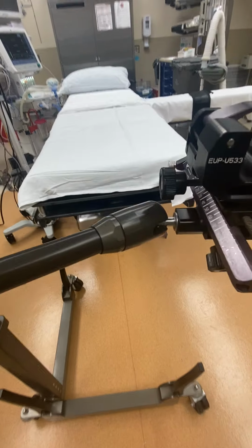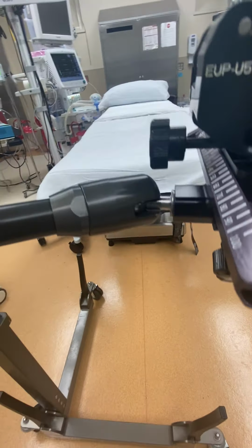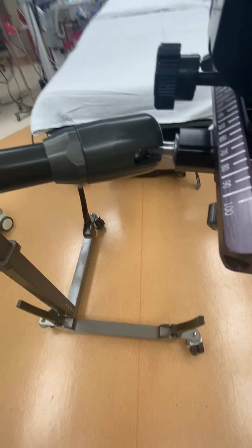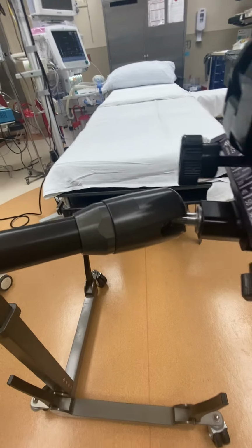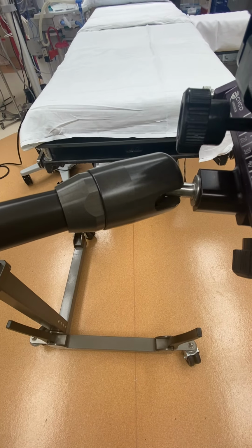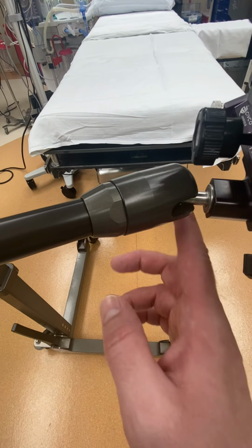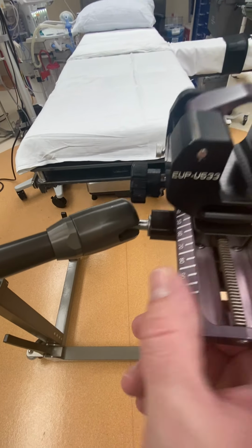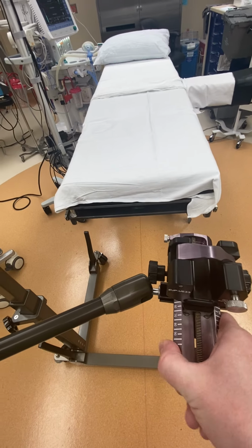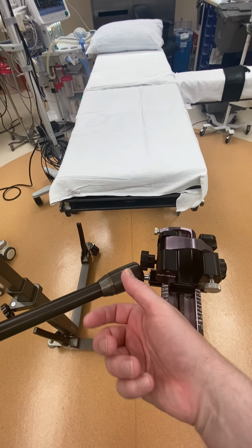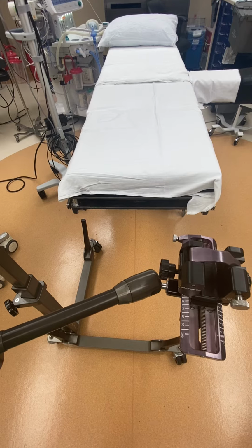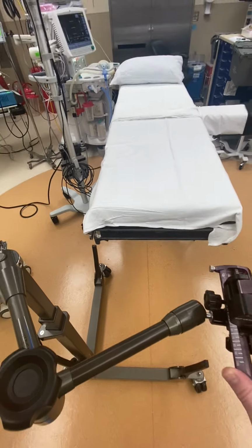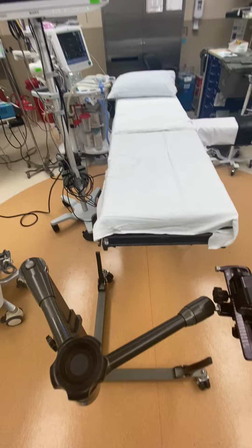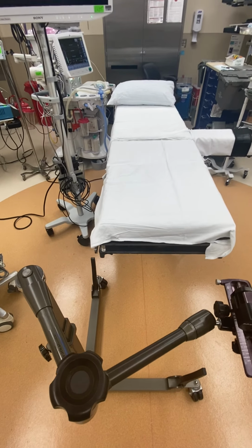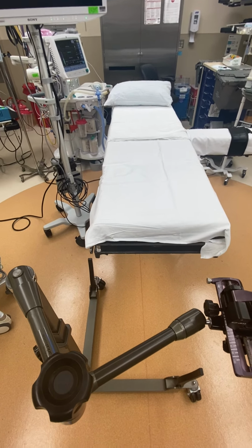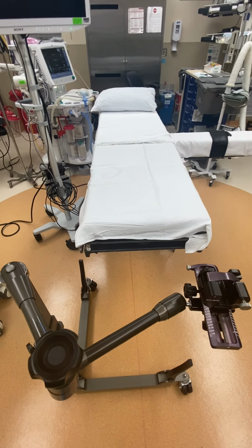Also, there's a little notch here on the arm where the cradle is jointed. You want to make sure that's facing back. You don't want it to be facing forward or down or up. It has to be facing kind of back toward you, and that allows you to angle the cradle, which is useful when the urologist is trying to center the prostate on the probe. And you can watch those other videos, which go into more of the centering setup that we do for axial and sagittal. It's a similar kind of thing whether you're using the stepper or the Artemis.